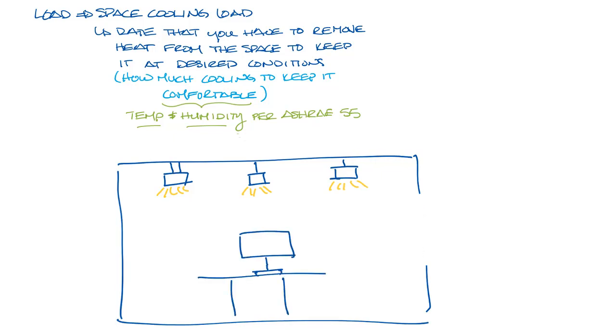If there's a window, you might have solar load coming in through the window. Or if the space next door has a high heat load for some reason, you might have some transmission coming through there. Or you might have heat gain from outside air coming into the space through doors or small cracks in the building called infiltration.